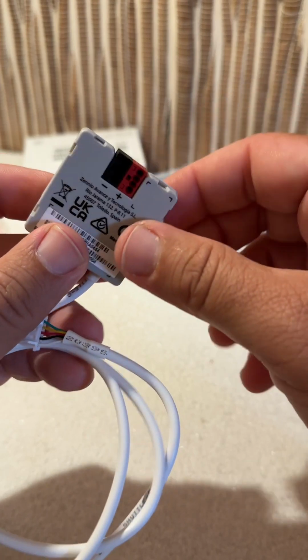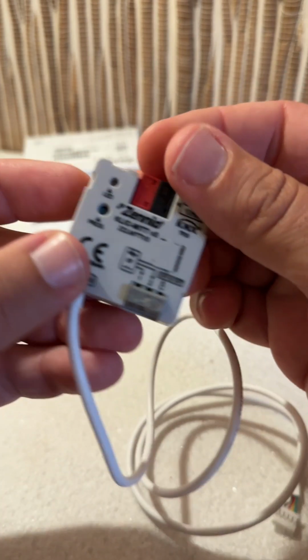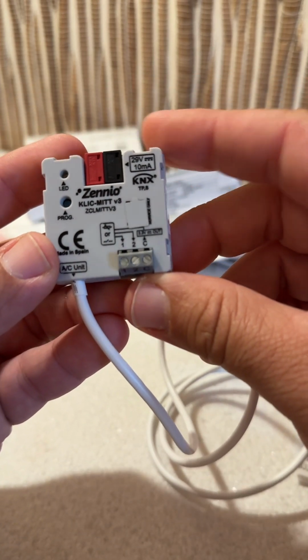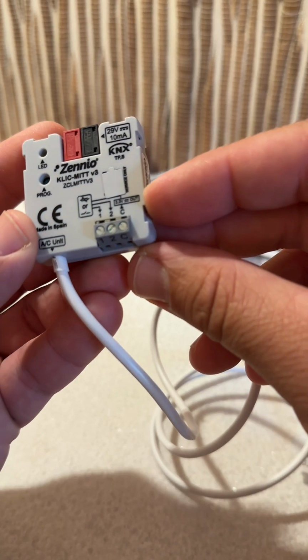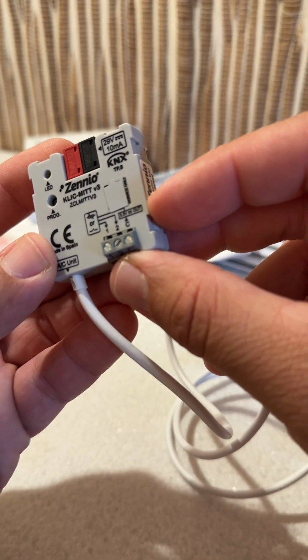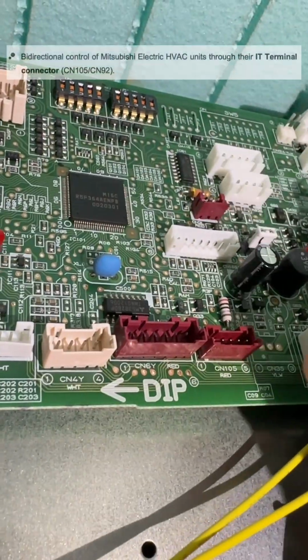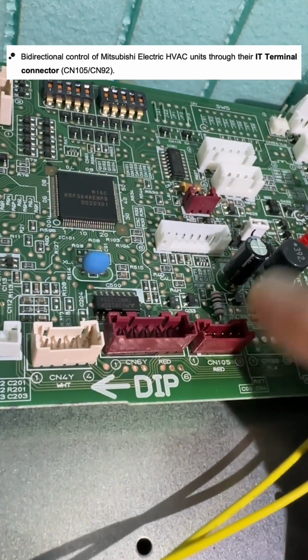In addition to the KNX bus connector, the gateway features two inputs that can be used for temperature probes, motion sensors, or dry contact binary inputs. The gateway must be connected to the Mitsubishi IT terminal connector CN105.